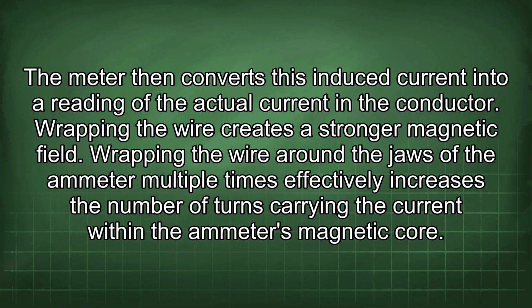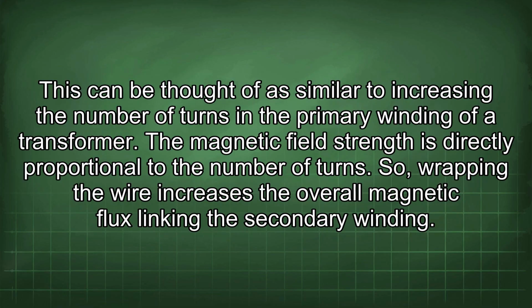Wrapping the wire creates a stronger magnetic field. Wrapping the wire around the jaws of the ammeter multiple times effectively increases the number of turns carrying the current within the ammeter's magnetic core. This can be thought of as similar to increasing the number of turns in the primary winding of a transformer. The magnetic field strength is directly proportional to the number of turns. So, wrapping the wire increases the overall magnetic flux linking the secondary winding.